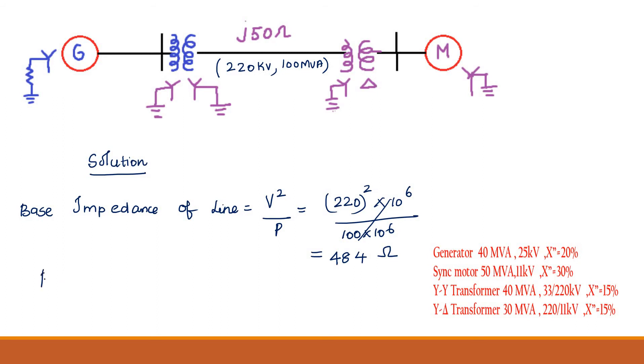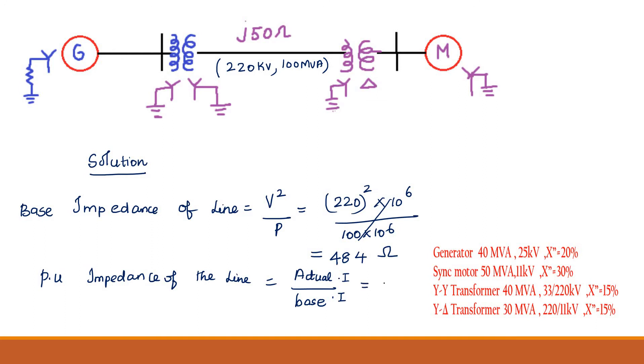Next, I am going to find out the per unit impedance of the transmission line. Per unit equals actual value divided by base value. The actual impedance given is J50 ohm, divided by the base impedance of 484 ohm. So, the answer is J0.1033 per unit. These are the per unit values for the transmission line.